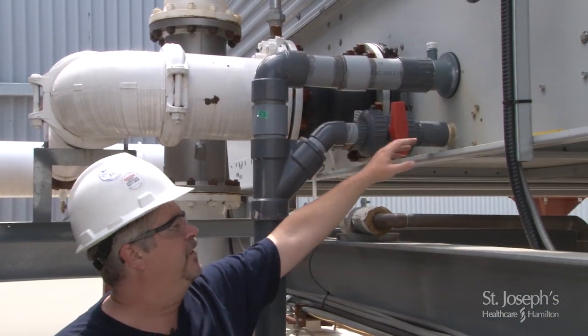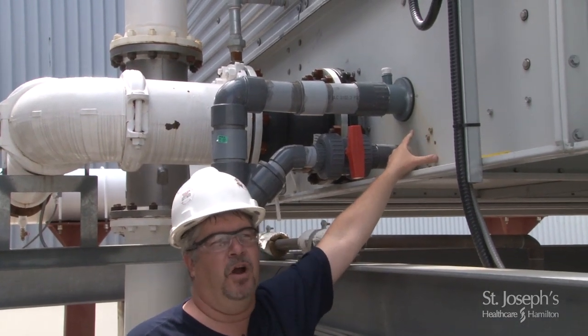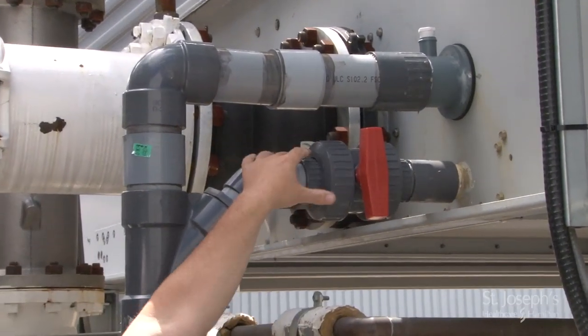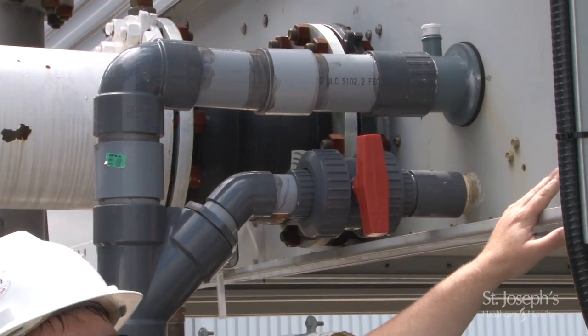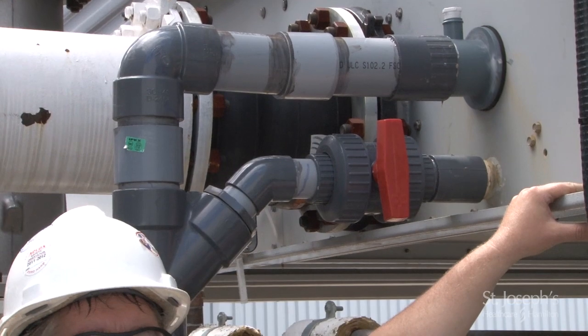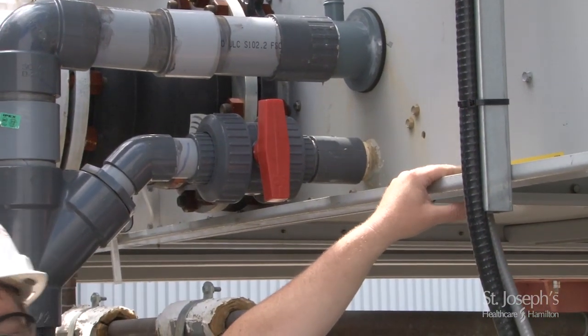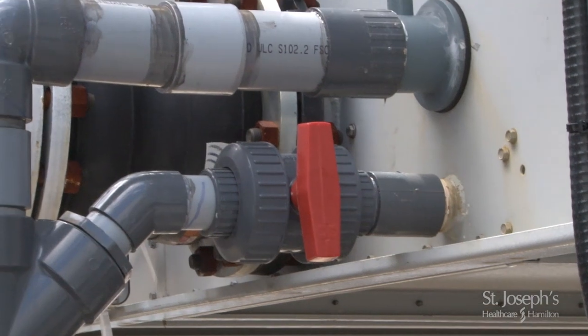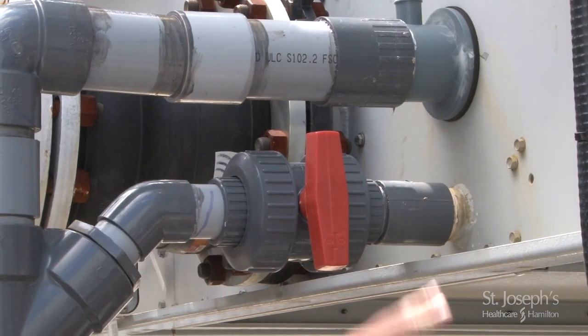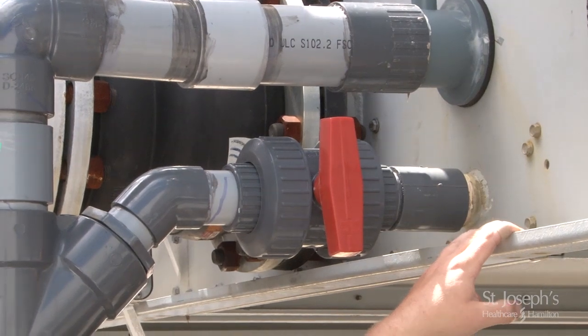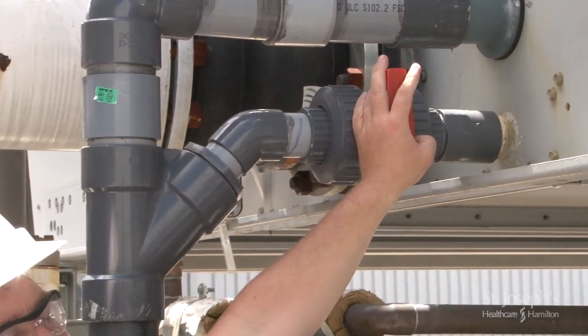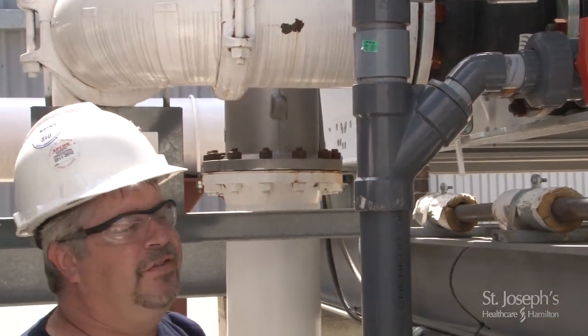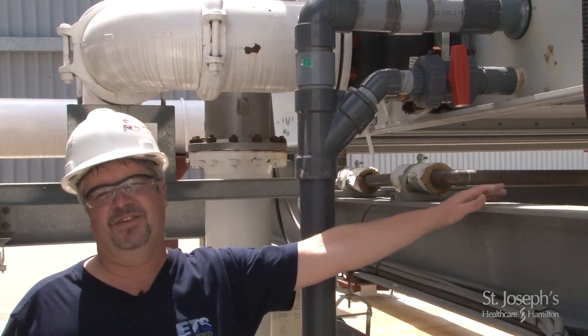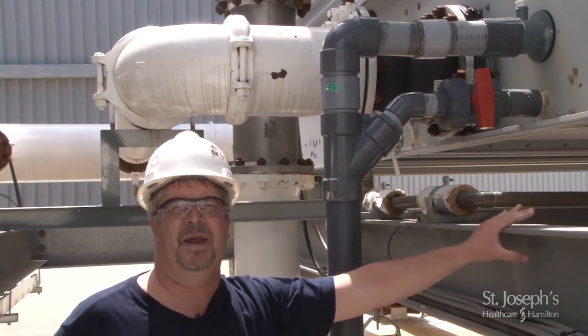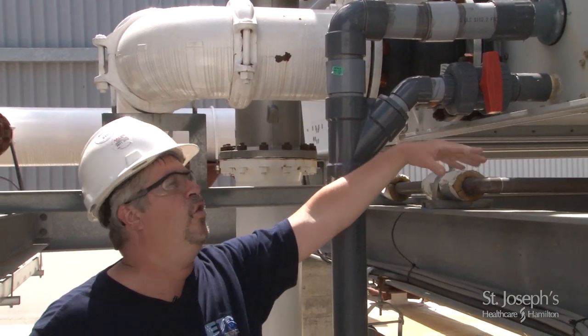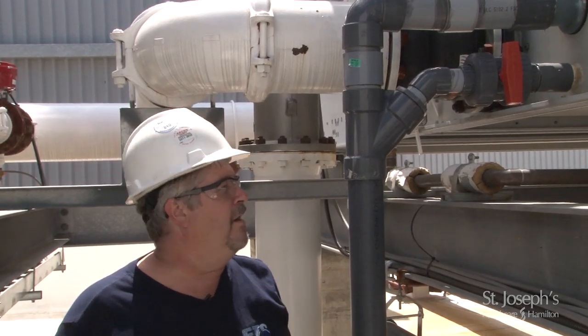Below it, and basically mounted right at the bottom of our cold water basin, is our drain valve. We do want to do periodic, annual maintenance on these cooling towers, which will require them to be shut down. Individually, we can shut them down, drain them down and clean them properly. So when we're going to do a procedure like that, we can open up the drain valve. That will drain this sump down and allow us to get inside and clean any dirt and debris that might have settled within the basin of the cooling tower. Once we're done, we close that valve back up.